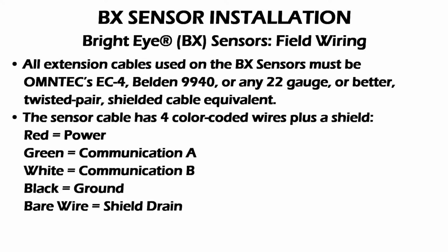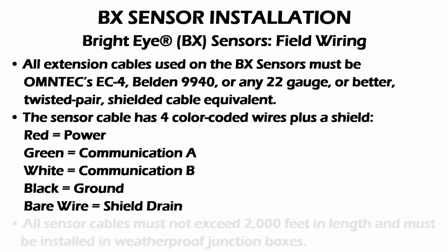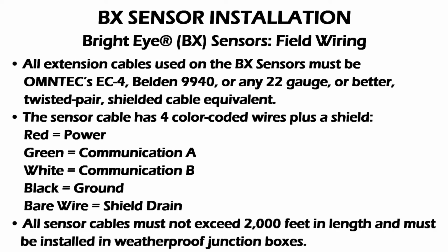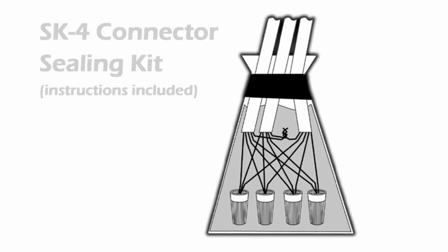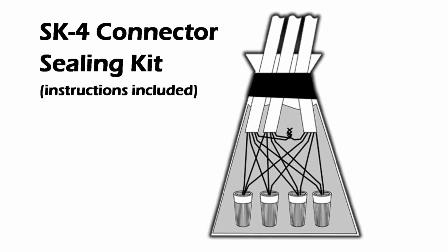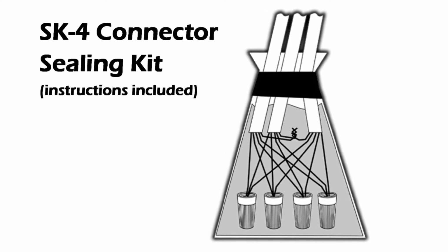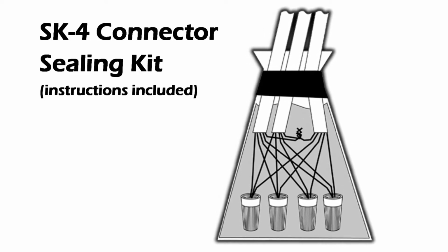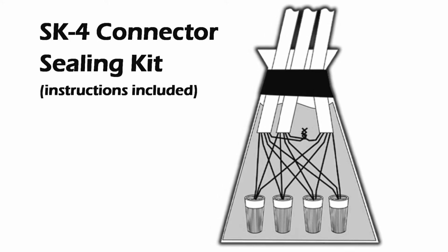The sensor cable has 4 color-coded wires, plus a shield. Red, which is the power. Green, which is communication A. White, which is communication B. Black, which is the ground, and the bare wire is the shield drain. All sensor cables must not exceed 2,000 feet in length and must be installed in weatherproof junction boxes. Make wiring connections and use the SK4 connector sealing kit for all splices. Instructions are provided with the kit. This completes the sensor installation section.